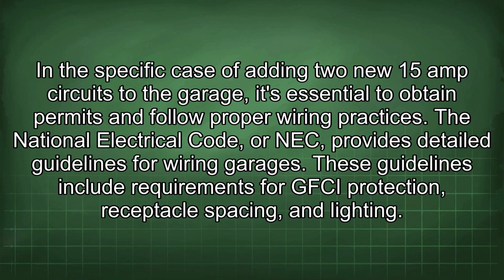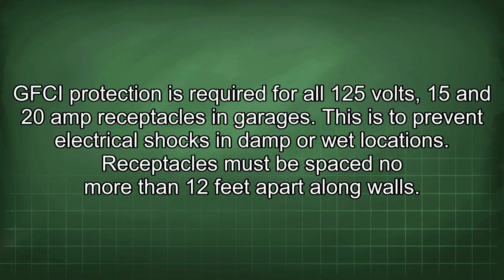In the specific case of adding two new 15-amp circuits to the garage, it's essential to obtain permits and follow proper wiring practices. The National Electrical Code, or NEC, provides detailed guidelines for wiring garages. These guidelines include requirements for GFCI protection, receptacle spacing, and lighting. GFCI protection is required for all 125 volt, 15 and 20 amp receptacles in garages. This is to prevent electrical shocks in damp or wet locations.